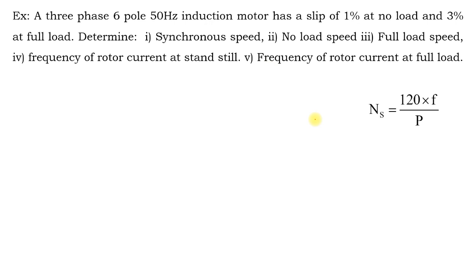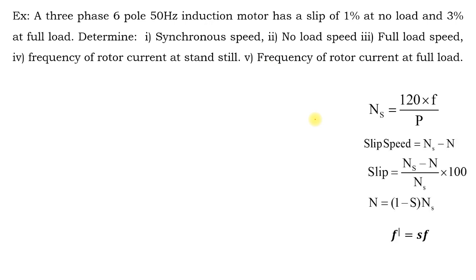To solve this problem these equations are sufficient. First, find synchronous speed: ns = 120 × f / P = 120 × 50 / 6 = 1000 rpm.